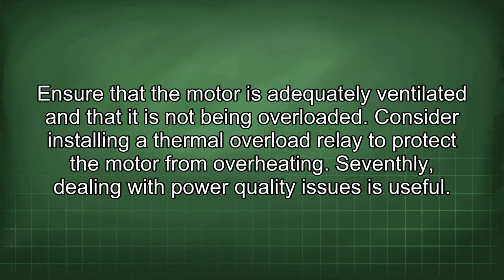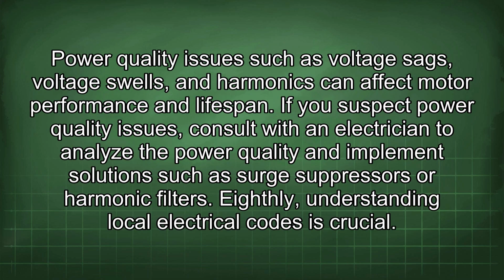Seventhly, dealing with power quality issues is useful. Power quality issues such as voltage sags, voltage swells, and harmonics can affect motor performance and lifespan. If you suspect power quality issues, consult with an electrician to analyze the power quality and implement solutions such as surge suppressors or harmonic filters.